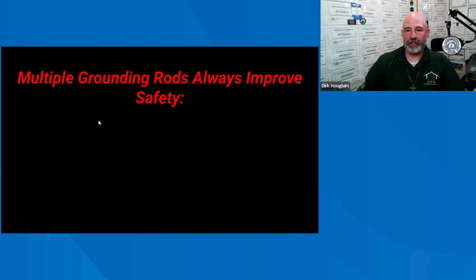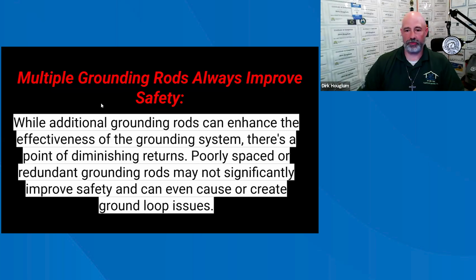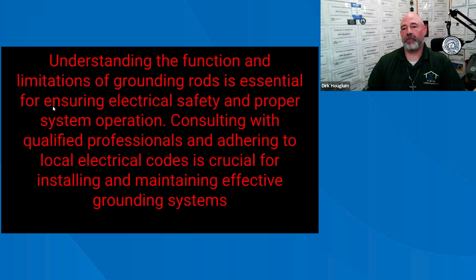Multiple grounding rods always improve safety - that is also a myth. Matter of fact, it actually causes more harm than good. Additional grounding rods can enhance the effectiveness of grounding systems, but there's a point of diminishing returns. Poorly spaced or redundant grounding rods may not efficiently improve safety, and they can create grounding loops, which could potentially cause injury or death, so we don't want that. Understanding the functions and limitations of grounding rods is essential for ensuring electrical safety and proper system operation.